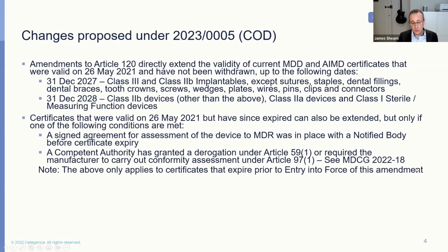Now, certificates that were valid on the application date, 26th of May 2021, but have since expired, can also be extended, but only if one of the following conditions is met. So a signed agreement for assessment of that device to MDR was in place with a notified body before the certificate expired, or a competent authority has granted a derogation for the device under Article 59(1) of MDR, or has required the manufacturer to carry out conformity assessment under Article 97(1) of MDR in accordance with the MDCG guidance 2022-18. The other thing to note is that this also only applies to certificates that expire prior to the date of entry into force for the proposed amendment. This is a date that we don't yet know because it hasn't yet been approved.